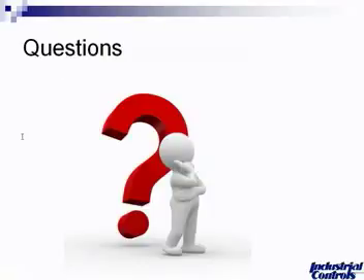Okay, great. We received another question in from Joe. Is one steam trap technology better than another? That's a good question. I don't believe one technology is better than another in steam trapping, but you will find that the condition of your system could make one of those better than another. So you have to analyze your steam system, you have to analyze your process, you have to bring those to someone like myself for industrial controls. For example, we would say in a process system that a float and thermostatic style trap would be the best way to go. No one trap can handle every condition that is out there in a steam system.